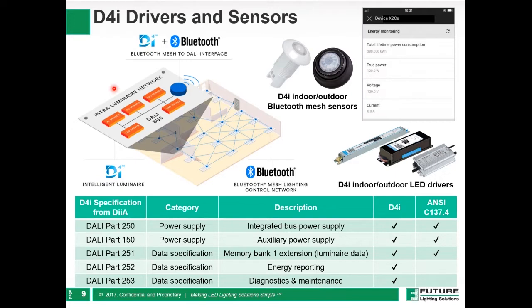What is D4i? It's essentially a partnership between the DALI Alliance, the DiiA, and the Zhaga group. They've created a specification for LED drivers that enables an integrated DALI bus, power supply, auxiliary power to power devices, and a memory bank so you can store luminaire information, such as the type of luminaire and the manufacturer.